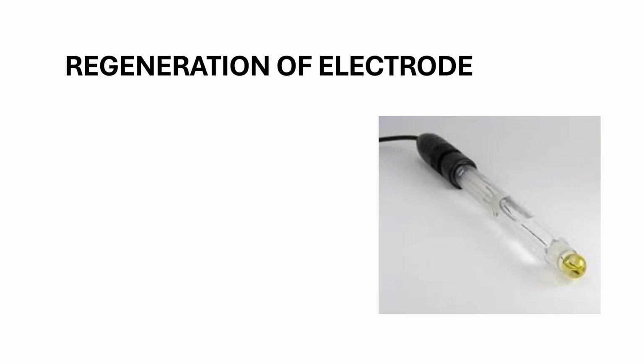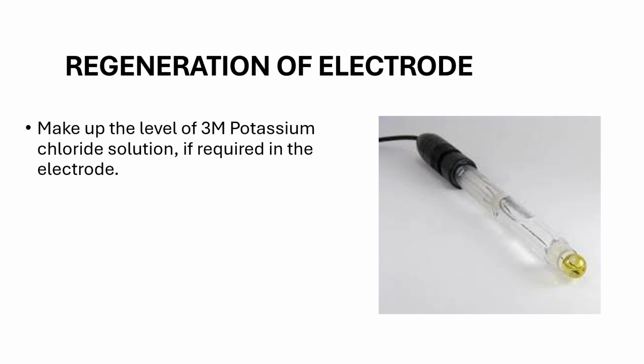Now here we will discuss the regeneration of the pH meter electrode. Regeneration of the electrode is necessary when the pH meter fails to meet the calibration requirements. This process helps to reactivate the sensing membrane and restore the electrode performance, right? First check the level of 3M potassium chloride solution inside the electrode. If you find it's low, then make up the level by refilling it with fresh 3M potassium chloride solution.